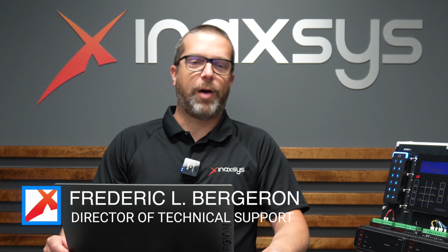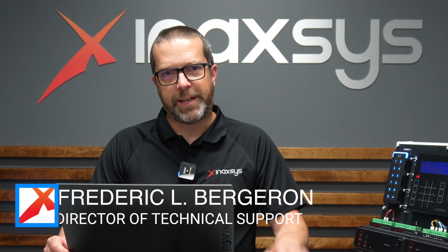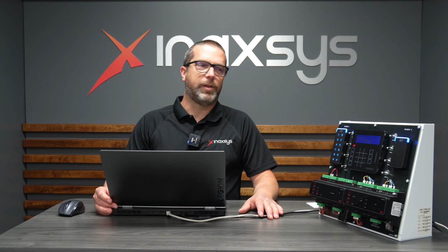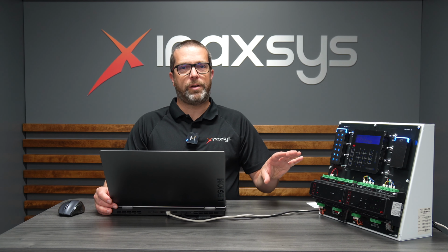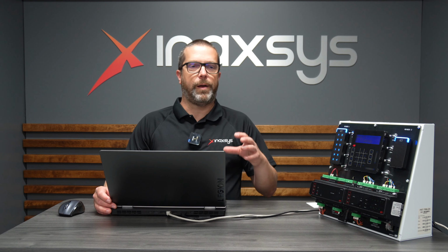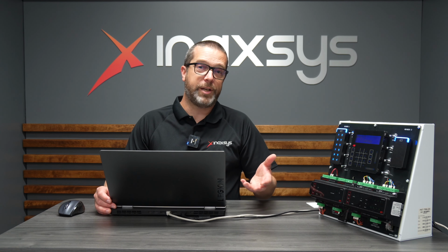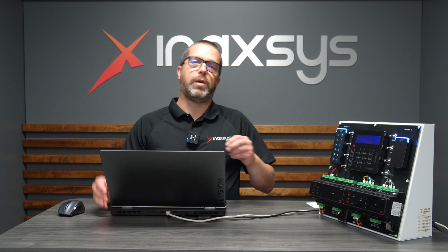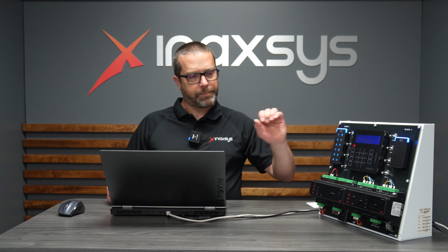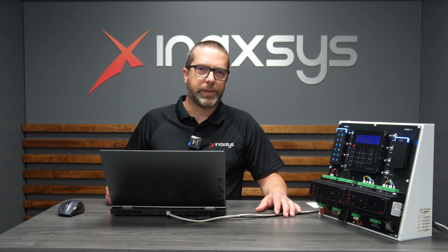In this video, I will show you how to program a basic elevator control system in the Protege WX system from ICT. Okay, so there are several steps involved in this configuration. Also, there are other levels of elevator control integrations. But today, let's start with the most basic scenario, when we're basically using a card reader to activate relay outputs that will then make floor buttons available.